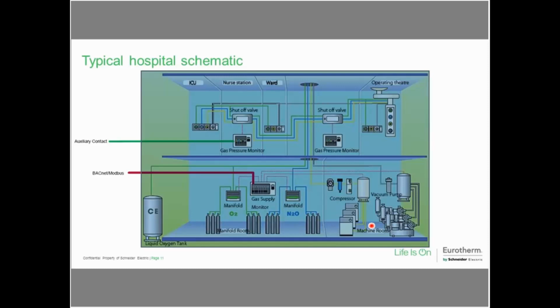BACnet adds another tool to access these different networks. Today, people are very familiar with setting up a Modbus network, but now instead of having to set up a gateway if you're trying to integrate with BACnet, it's an embedded protocol that's being used right from the get-go, so it's very easy.